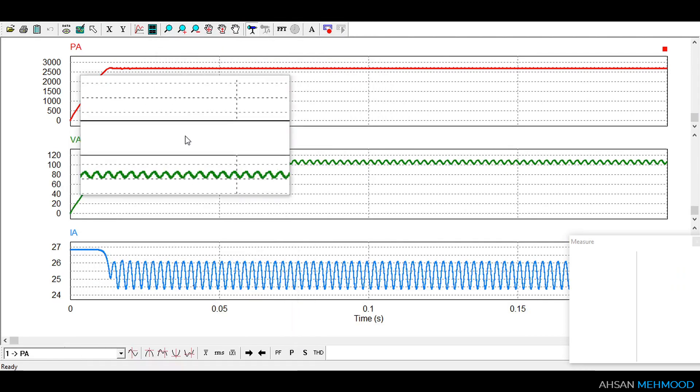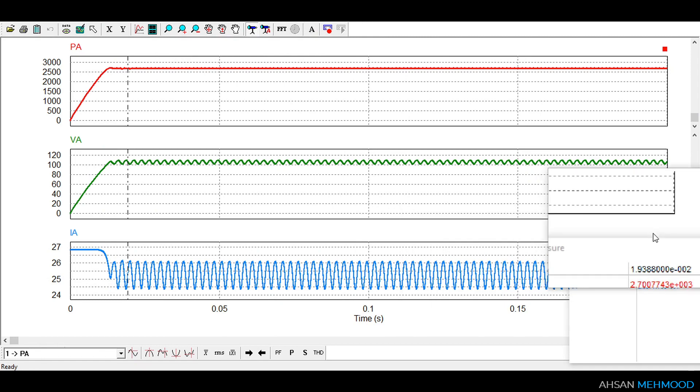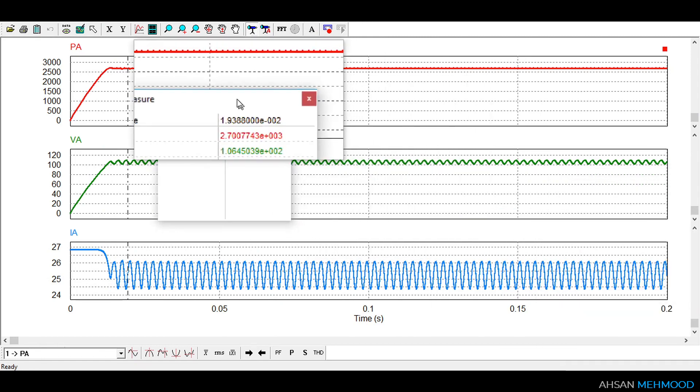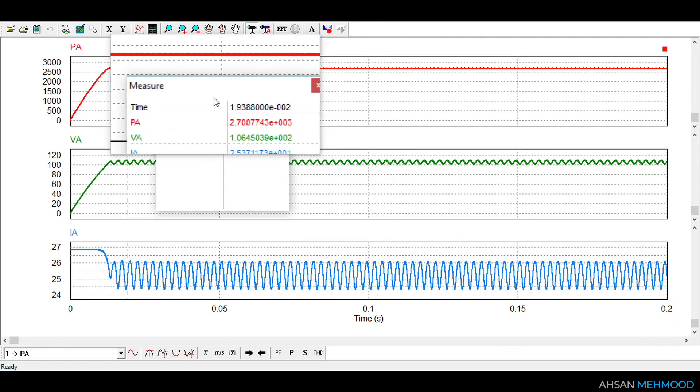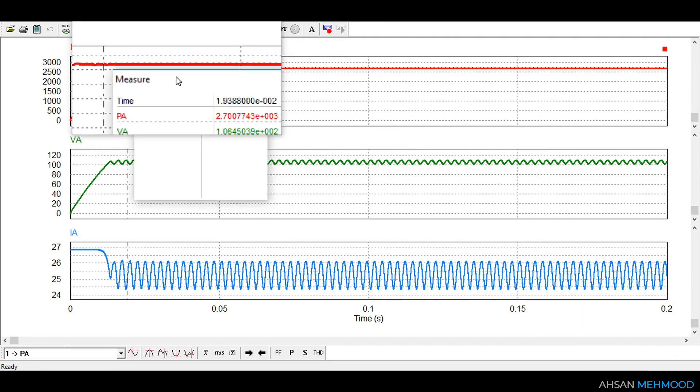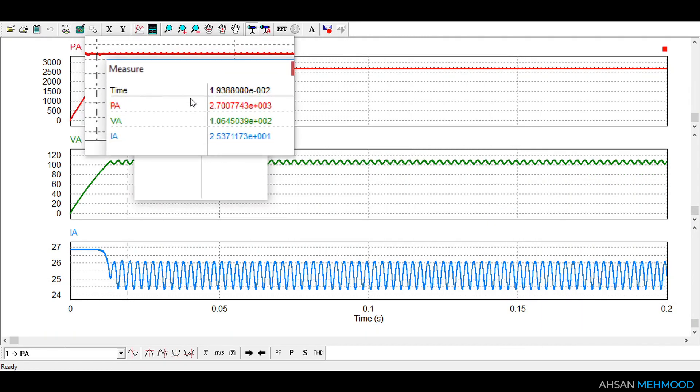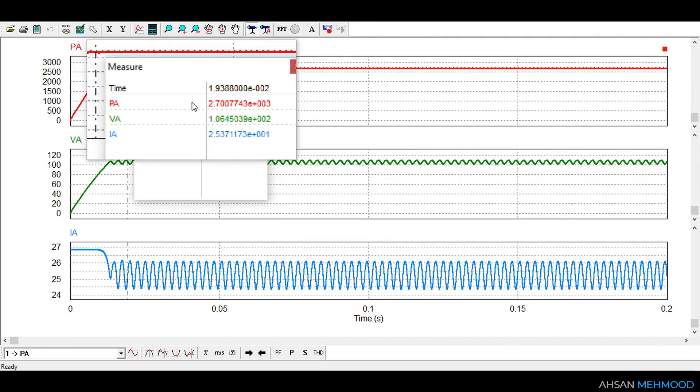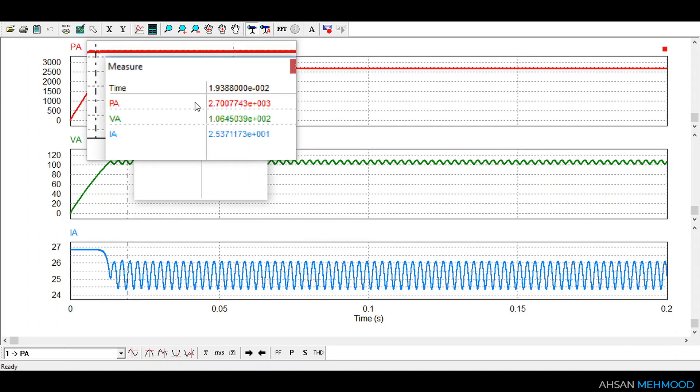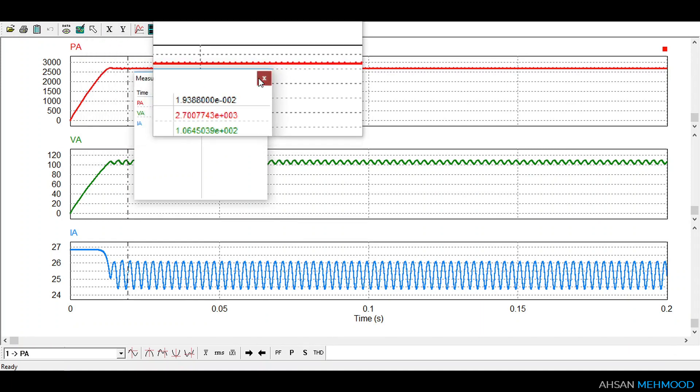As you can see array is operating at around 2700 watt which is the maximum power point of the PV array. At this point array voltage and current are 106.4 volt and 25.4 ampere respectively. This shows that our incremental conductance algorithm is working perfectly.